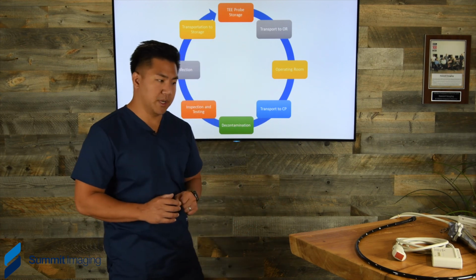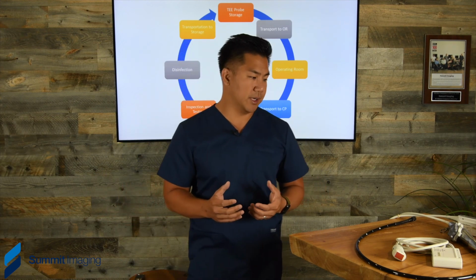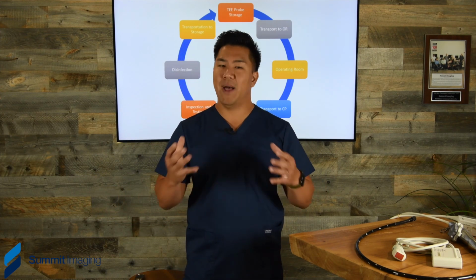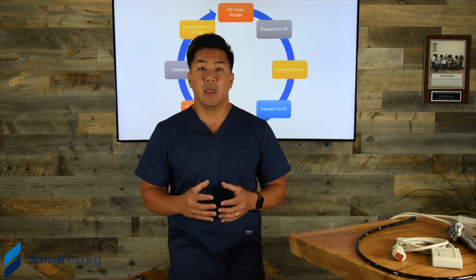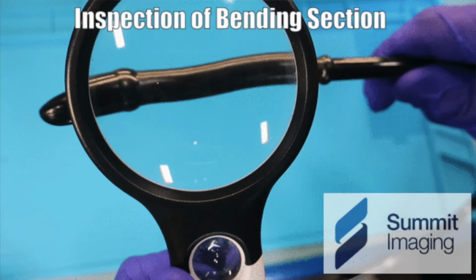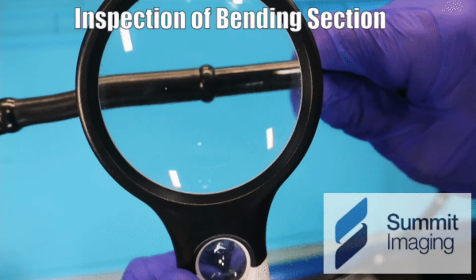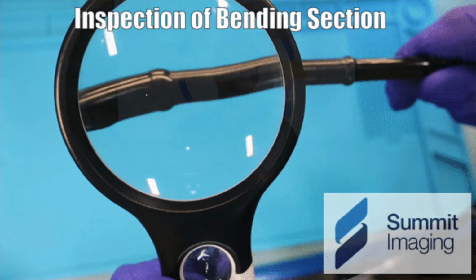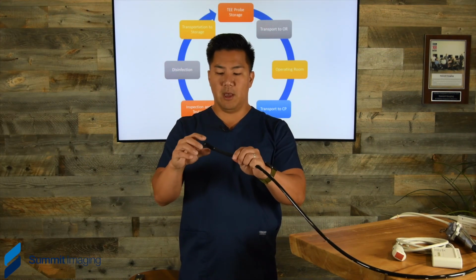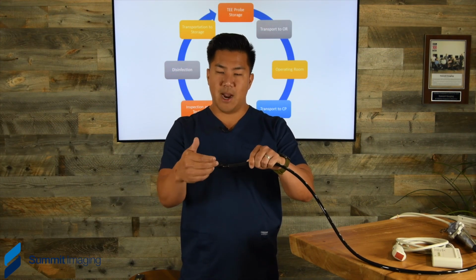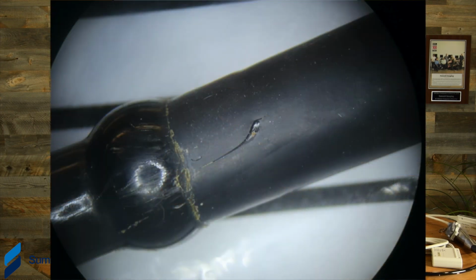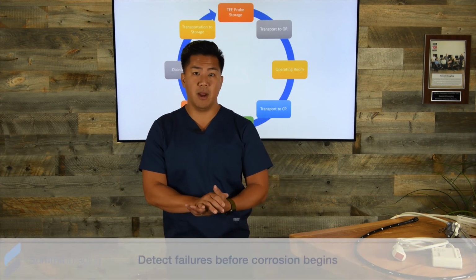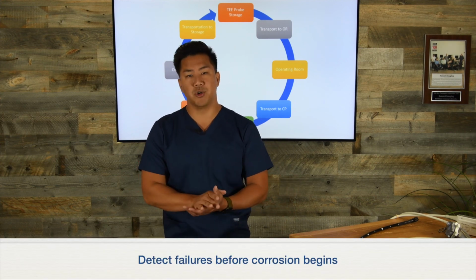So what do you do during inspection and testing? Well, we go to a lot of facilities and we recommend getting a high-powered magnifying glass and a nice light and training those techs that are decontaminating your equipment to look for micropunctures, abrasions, cuts, fractures, gouges on the tip, and if there's any thought that there could be damage, get it in for repair as quickly as you can. The faster you can get it into repair, it prevents the corrosion from occurring.